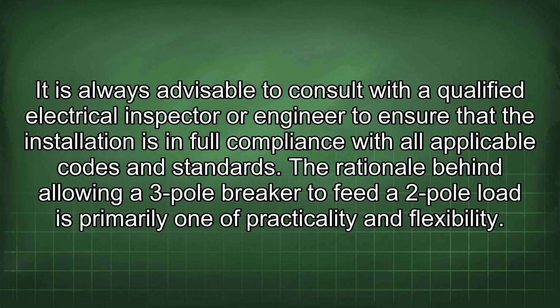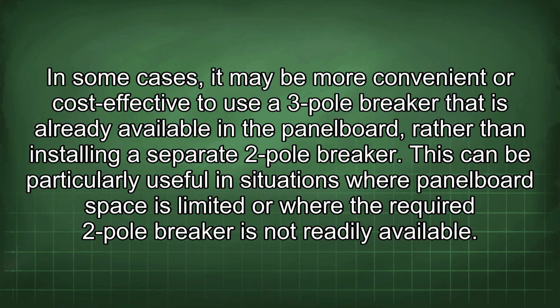The rationale behind allowing a 3-pole breaker to feed a 2-pole load is primarily one of practicality and flexibility. In some cases, it may be more convenient or cost-effective to use a 3-pole breaker that is already available in the panel board, rather than installing a separate 2-pole breaker.